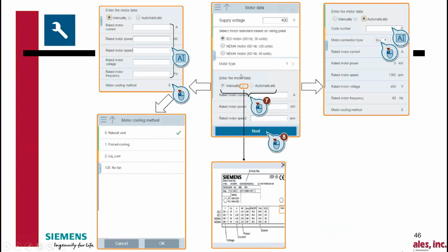If we pick dynamic or standard, you're next going to come up to this motor data pop-up: the supply voltage of the motor, and your IEC, NEMA, or NEMA with SI units. I've got a Siemens motor here, so I'm going to use the SI units. Then we've got motor data entry. With manual, a menu pops up to the left where you put motor current, motor power, voltage, frequency, and then there's a selection of ventilation. Typically we're going to be naturally ventilated.